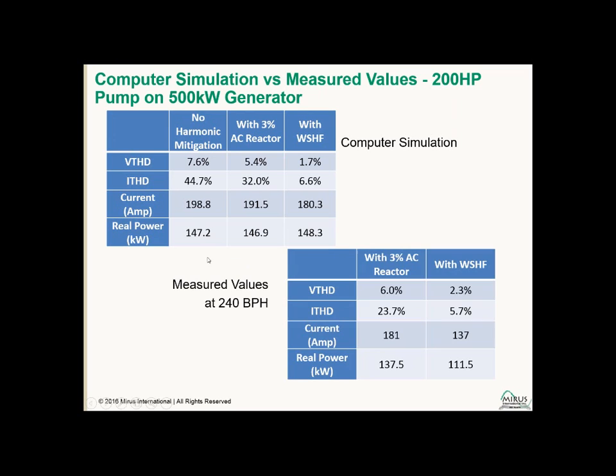You can see the simulation shows a slight increase in power because there are some additional losses with the added filter. However, in the actual installation, when we measured the power consumed by the pump, when it was delivering the same 240 barrels per hour, that was the flow rate targeted by the customer, there was a substantial reduction in the power consumption.